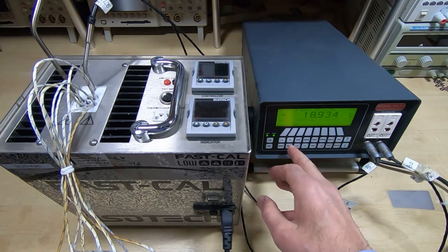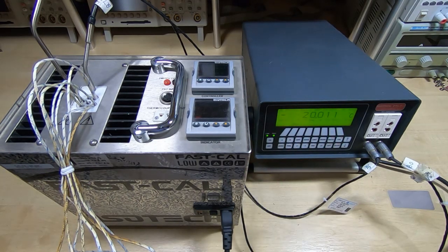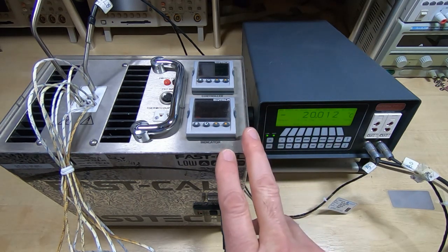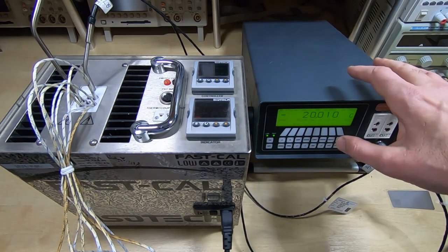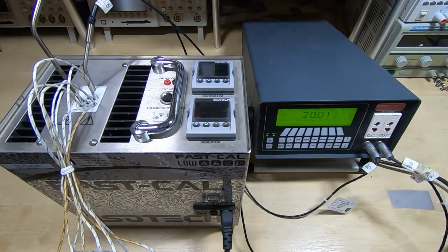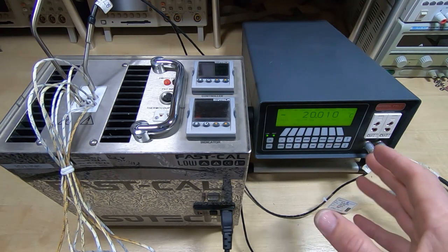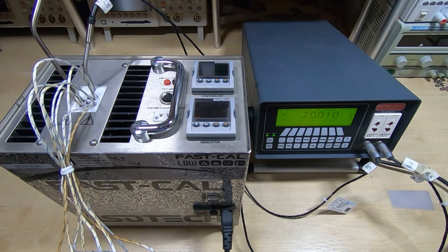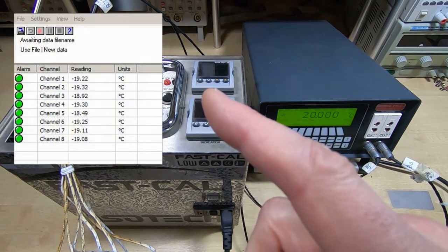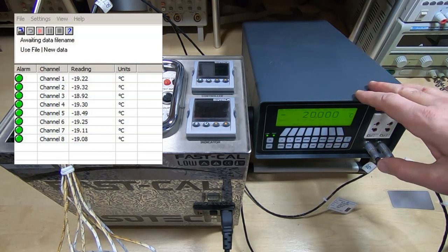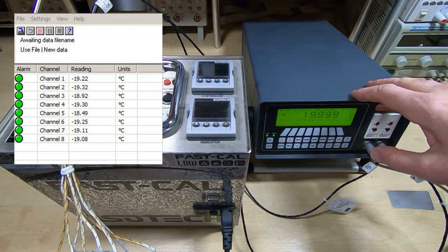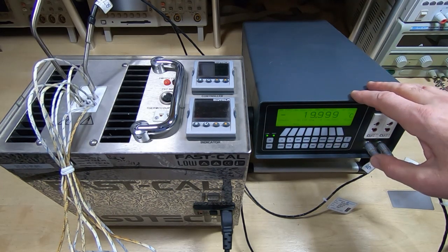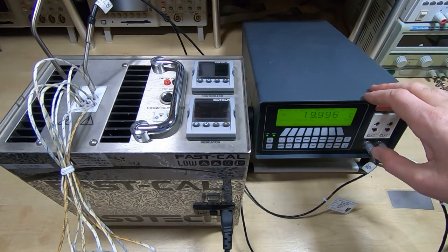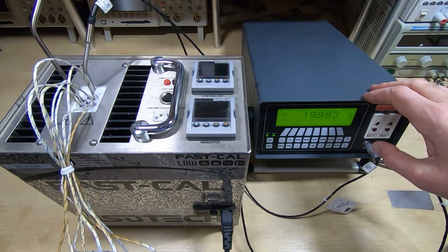But if we look at the 2 values, we've got minus 19 degrees and minus 20. This is set to minus 20, but that's an arbitrary value. It just drives fairly close to that, but it's the UKAS reference that we use for the actual readings. So that'll give us a rough value here of minus 19.5. So I'll take a screenshot of the capture software so we can get a current reading. Okay, so you can see the values here, and they are fairly close, so within half a degree of what we're aiming for. Thermocouples in this mode are not generally particularly accurate at low temperatures, but we are within the acceptable range here, so it can be deemed to be valid.